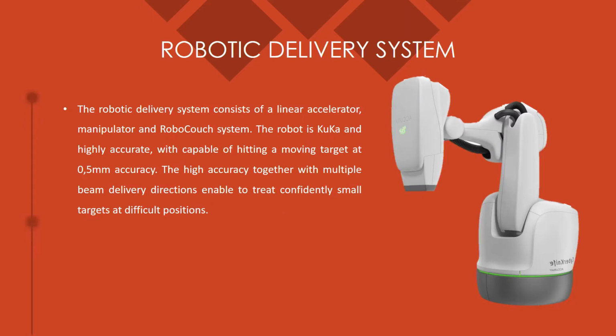Robotic delivery system. The robotic delivery system consists of a linear accelerator, a manipulator, and a RoboCouch system. The robot is a KUKA, which is also commonly used in the car industry. This model is, however, extensively modified to work as a medical device for radiotherapy. The robot is highly accurate, capable of hitting a moving target with 0.5 mm accuracy. The high accuracy, together with multiple beam delivery directions, enables treatment of small targets at difficult positions.